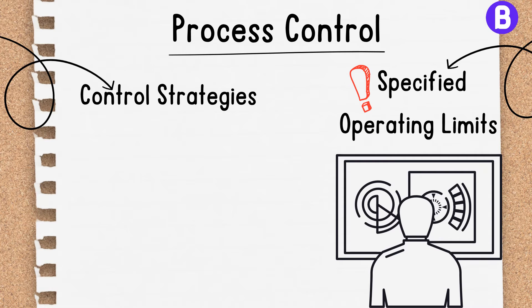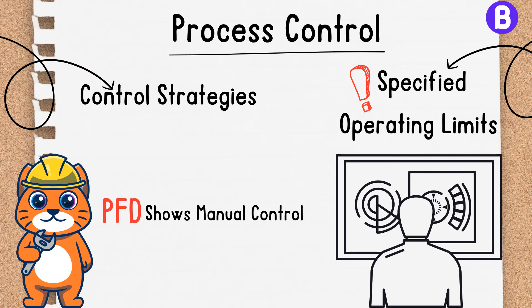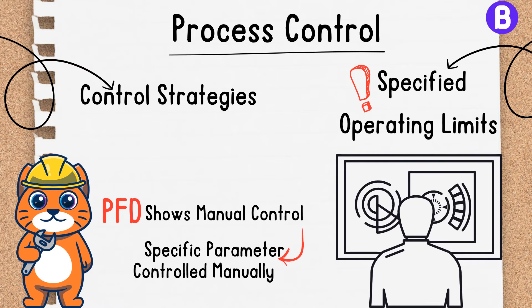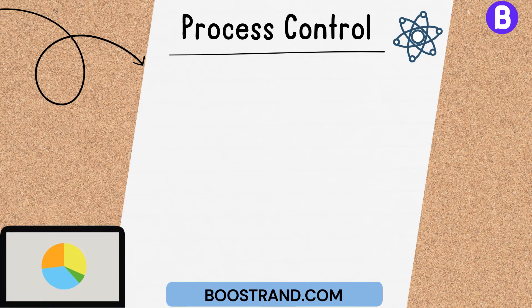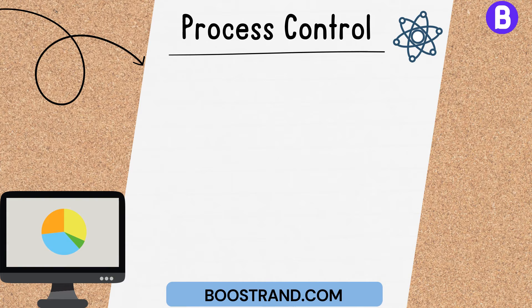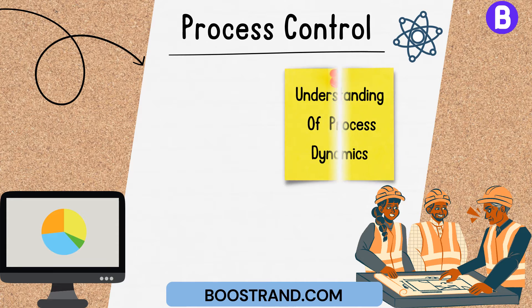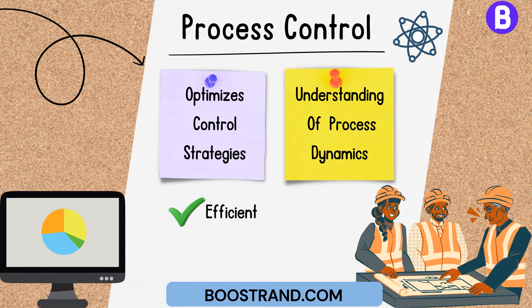In addition, a PFD also shows manual control. If there is a specific parameter that is controlled manually by the operator, the PFD shall show the manual valve and the instrument from where the operator shall see the reading. Reflecting the control schemes on a PFD gives engineers and operators a holistic understanding of the process dynamics and optimizes control strategies for efficient and safe operation.